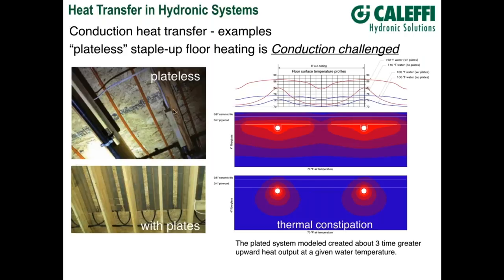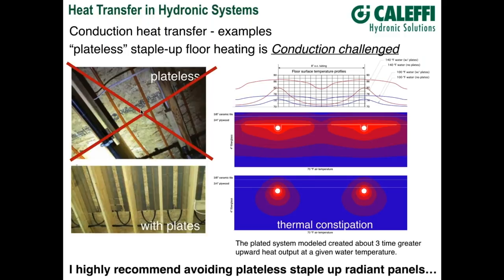Imagine 150 to 160 degree water in that PEX tubing — the tubing is going to expand and become more flexible than at room temperature, so it'll droop away from the surface. That cuts pretty much any conductivity except perhaps directly where it's stapled. This is not a system I would recommend. I highly recommend avoiding plateless staple-up radiant panels.